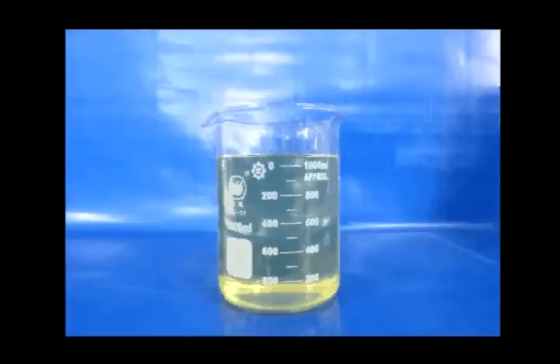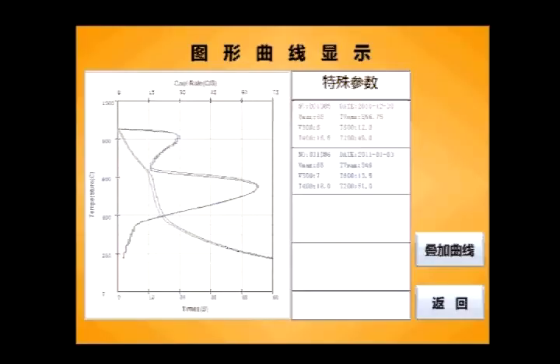The stabilizing quenching treatment of the probe: stabilizing treatment should be carried out for 2 to 3 tests or more. A stabilizing quenching treatment uses clean oil to reduce harm to the probe and to assist in the formation of a better dense oxide film. Probe in the stabilization process: if the two experimental results are the same, the stabilizing treatment is successful. Next, the probe can be calibrated. Of course, if stabilization is not successful, the treatment should be repeated, usually 2 to 3 times.